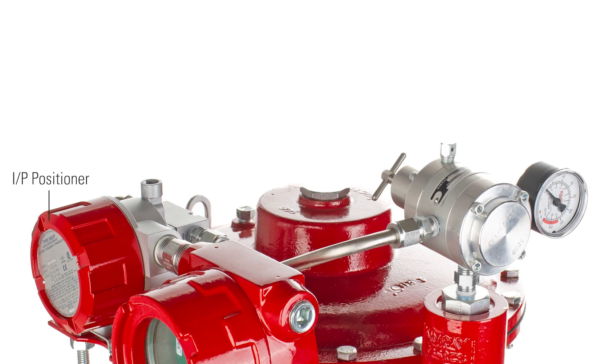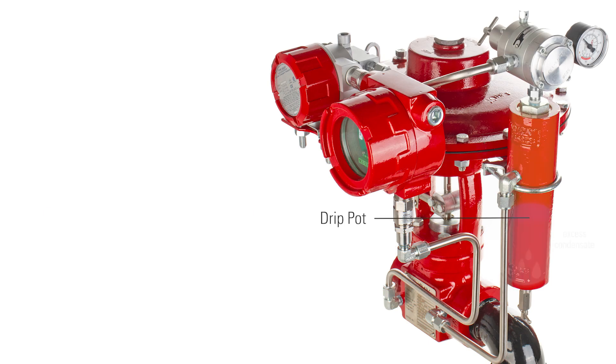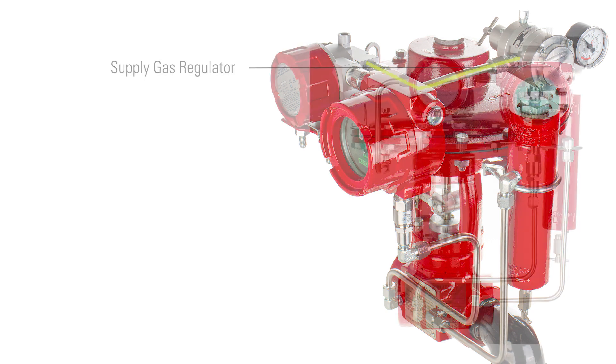The I/P positioner receives this electrical input as well as the supply gas input. The supply gas input comes through the drip pot, which removes excess condensate, and the supply gas regulator, which keeps the pressure to a manageable level to allow adequate feed to the input of the I/P. The I/P positioner converts that electric input signal to a corresponding 6 to 30 psi output signal and sends that level of supply gas to the high-pressure control valve.